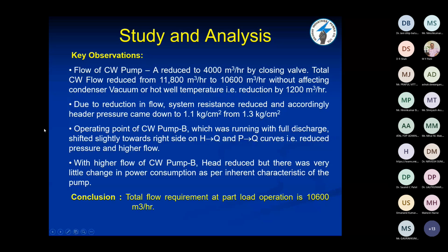Now these are the observations. Flow of cooling water pump A reduced to 4,000 meter cube per hour by closing the valve. Total cooling water flow reduced from 11,800 meter cube per hour to 10,600 meter cube per hour without affecting condenser vacuum or hot well temperature. That is a reduction of 1,200 meter cube per hour. That means 1,200 meter cube per hour was the excess flow that was going to the condenser, so we can reduce that much flow without affecting the generation. By reducing that much flow, we will be able to reduce the energy.